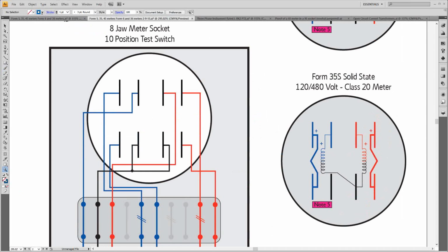If we look at the voltage across this potential coil when I'm using it on 4-wire delta, it would have 208 across it. I'd multiply this voltage by 2 when it's on 4-wire delta. On 3-phase 3-wire delta, this would have 240 volts, and so it doesn't multiply this voltage. So when it has 240 volts across it, it doesn't multiply that voltage. But if it has 208 across it, like on 4-wire delta, it's going to multiply that one.